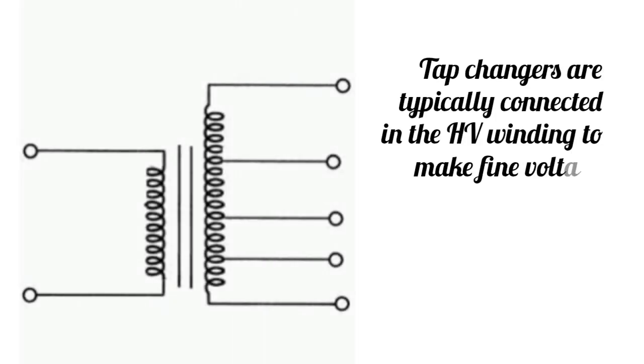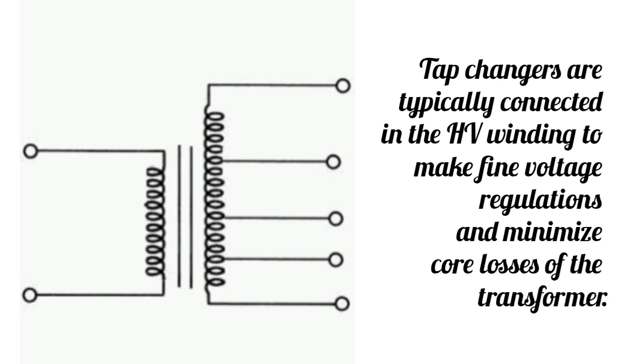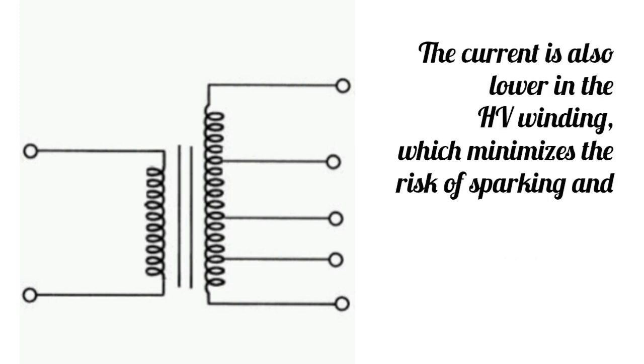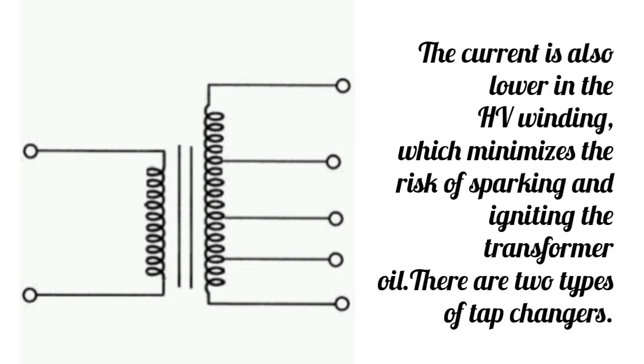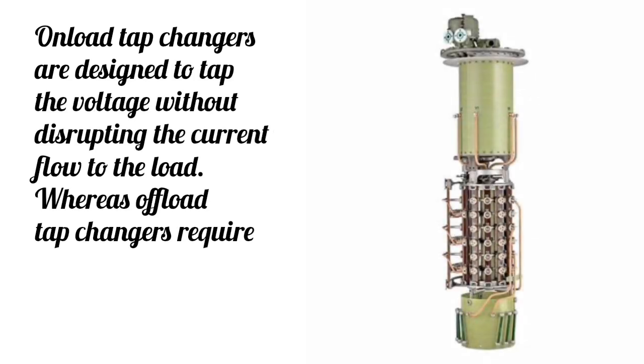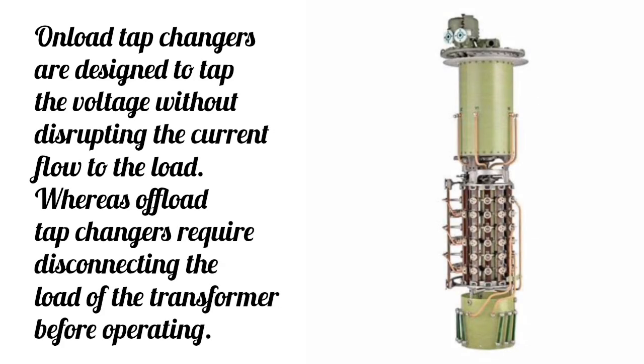Tap changers are typically connected in the HV winding to make fine voltage regulations and minimize core losses of the transformer. The current is also lower in the HV winding, which minimizes the risk of sparking and igniting the transformer oil. There are two types of tap changers. On-load tap changers are designed to tap the voltage without disrupting the current flow to the load, whereas off-load tap changers require disconnecting the load of the transformer before operating.